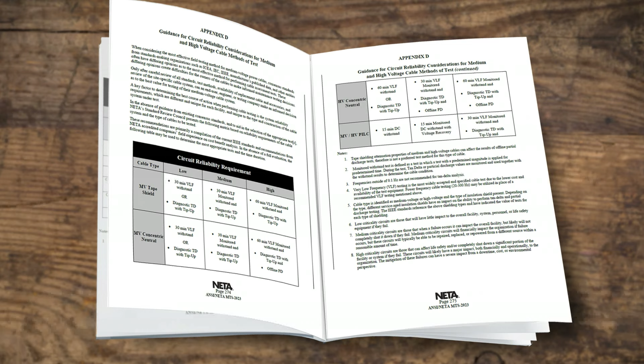Appendix D is guidance for circuit reliability considerations for medium and high voltage cable methods of test. We recognize at NETA that a lot of testing organizations or engineering firms are well versed in cable testing but may not know all the intricacies involved. So for a do-it-yourself situation, Appendix D gives guidance on what types of cables and tests we'd recommend based on the criticality of circuits, broken down into low, medium, and high criticalities.